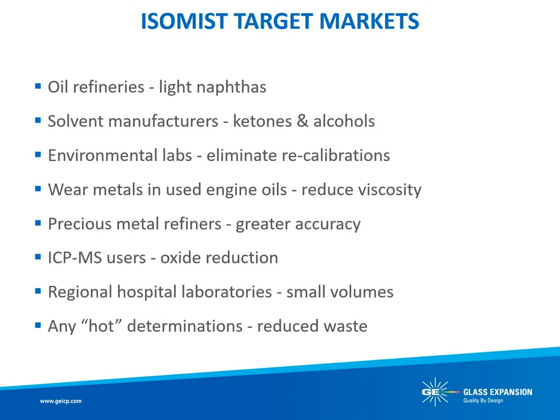Some of the industries for whom a temperature-controlled spray chamber would have the most value are listed here. Any laboratory that needs to analyze volatile solvents would benefit from the cooling capability of the Isomist XR. One interesting application is heating the spray chamber to reduce the viscosity of samples such as used engine oils or edible oils. In the precious metal business, by eliminating or minimizing drift between calibrations, higher accuracy and hence higher profitability can be achieved. The temperature can also be optimized for the best sensitivity of a particular precious metal.